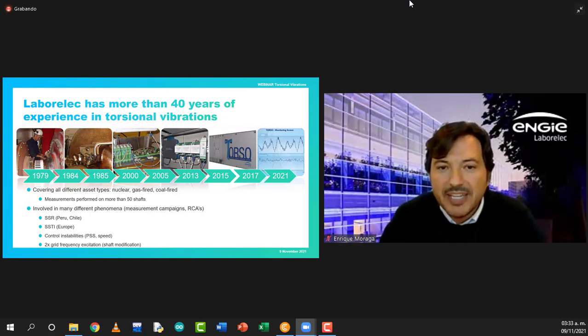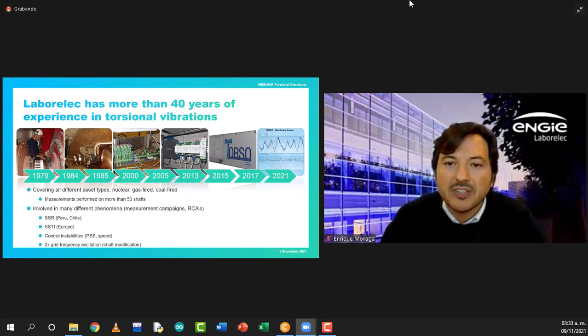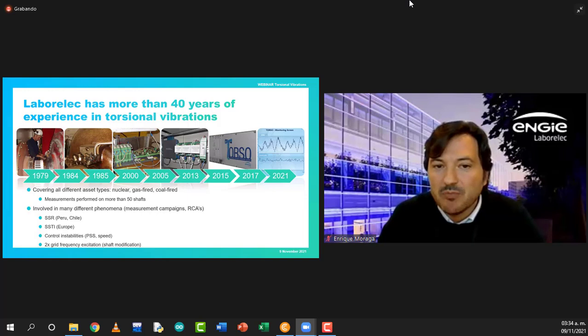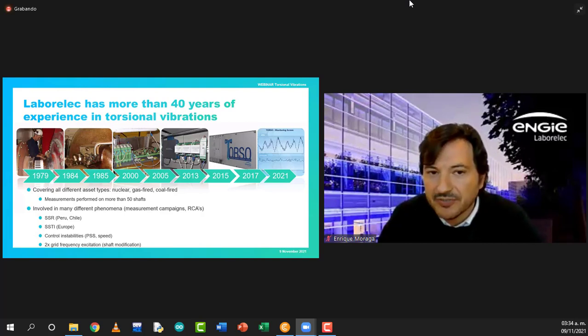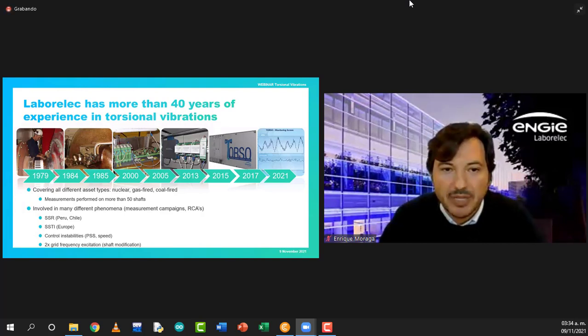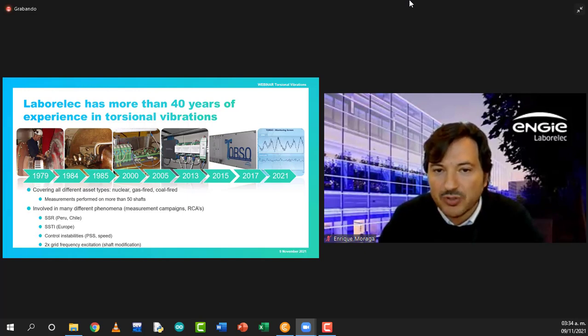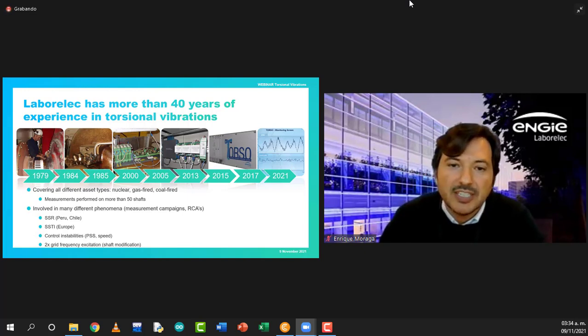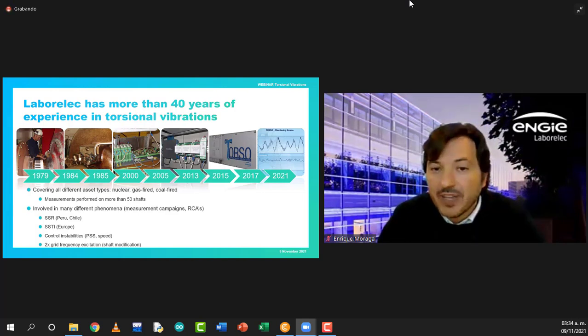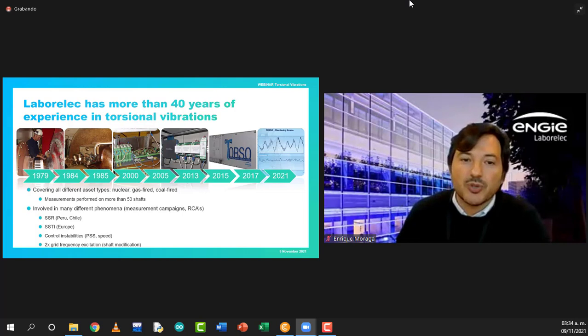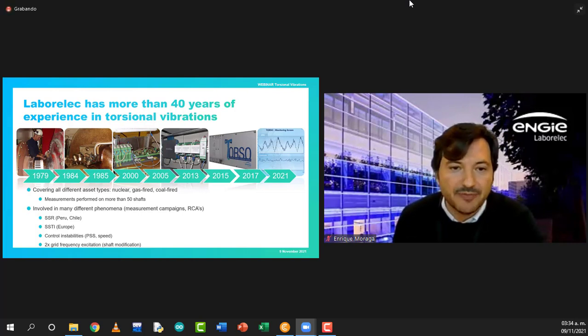Also, we have been involved in many different phenomena, such as subsynchronous resonance in South America, subsynchronous torsional interaction in Europe, control instabilities with the PSS, and also two-time grid frequency excitation. I have to say that during this time, we have been involved in 6 root cause analyses for catastrophic failures caused by torsional vibrations, in which some of them, and that is one of the big problems, required almost 2 years for rotor replacement. So it was a really, really huge problem for the power plant. For sure, and of course, none of them had a torsional vibration monitoring and protection system like we are presenting here today.